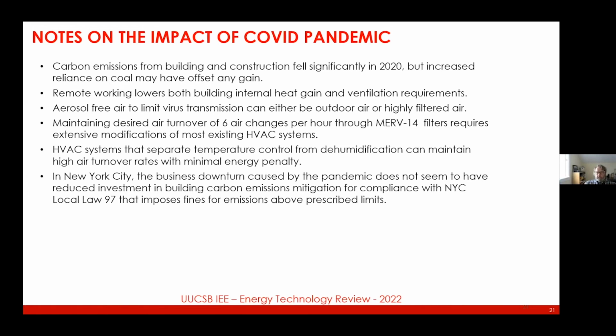In dehumidifying climates, our conventional VAV system keeps a constant supply temperature to control the dew point and varies its cooling capacity by varying the airflow. However, much of the time, that system will be operating at far below the 6 air changes per hour required to take the aerosols out of the air. So by separating, you do the dehumidification through the outdoor air ventilation stream, which is constant, and then do the sensible temperature control with turnover through some local fan coil or something like that, where you can vary the supply air temperature to vary the capacity and not vary the airflow and thus the turnover across the filters.